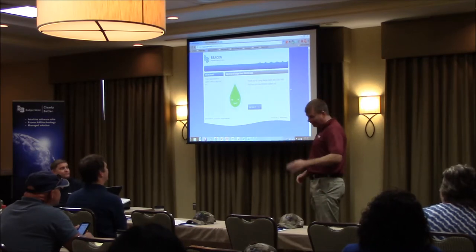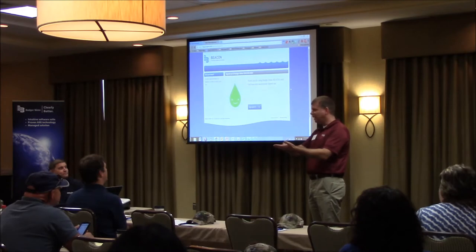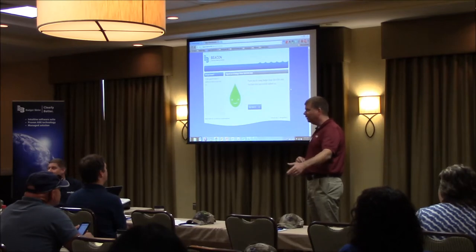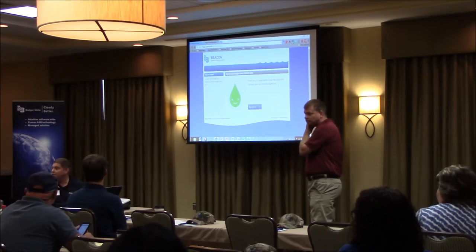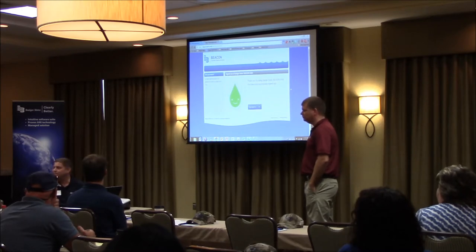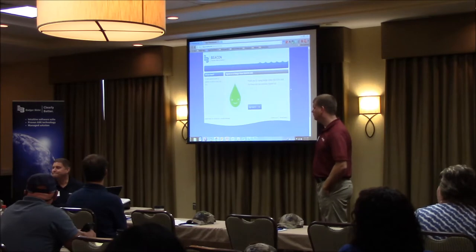He said, it's just crazy, after y'all changed that meter out, I got this leak. I said, no, you didn't. I logged in on my smartphone, and I said, all right, here it is right now. Here's your usage. What time do you close also? Here's where your water usage goes down. This is what your leak is. I said, is that the same flow rate I just showed you on the meter? He was convinced then, and he was very appreciative of it. But yeah, on the browser on your smartphone, you just log in. It's a smaller screen, but yeah, we've been able to access it in the field as well.